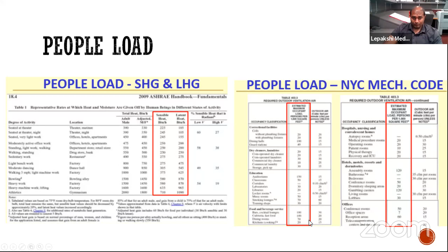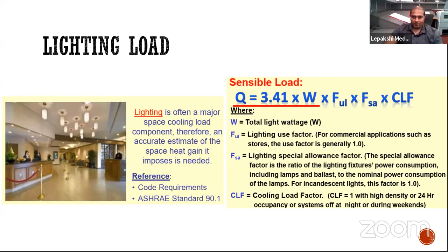Again, for lights, you'll have tons of lights if it's a skyscraper, and they'll have a certain wattage. You have to calculate the heat they give off. If it's 1 or 2 watts, that's okay, but multiply that by however many bulbs there are, maybe 1,000 light bulbs, and it becomes significant. So you have to figure that out too. ASHRAE comes into play again with their standards, and you come up with the load using formulas as shown here.